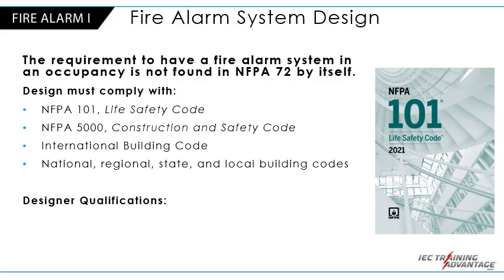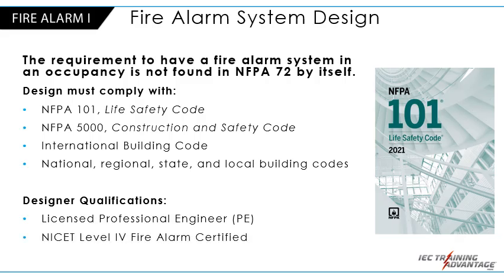Designer qualifications for these systems: licensed professional engineer or NICET level 4 fire alarm certified. Qualifications will vary greatly through the 38,000 jurisdictions in the U.S. Some jurisdictions require a PE stamp on plans for buildings over a certain size or cost, where others may permit NICET level 4 fire alarm technicians to design some systems.